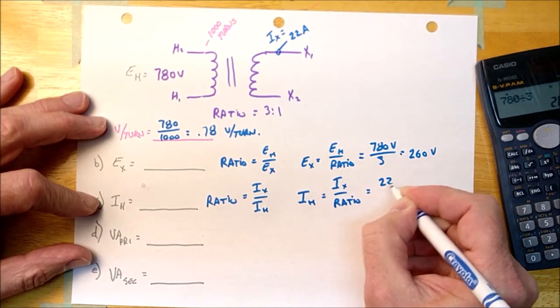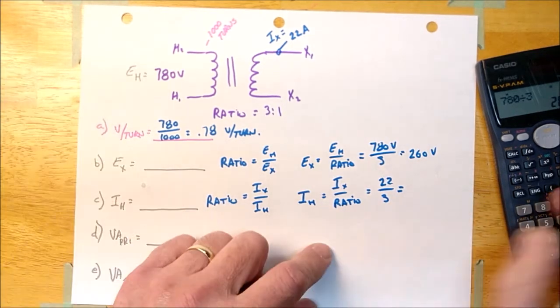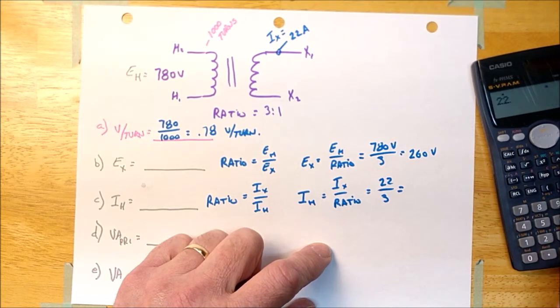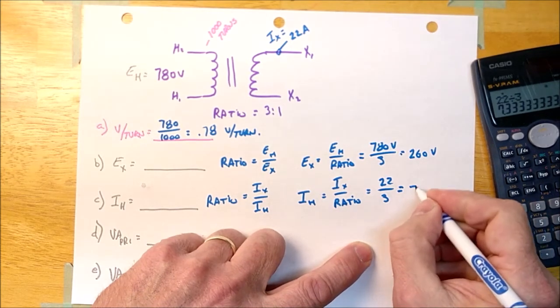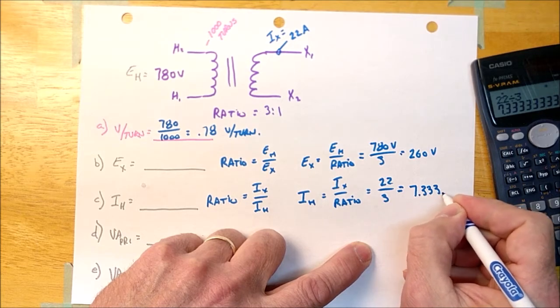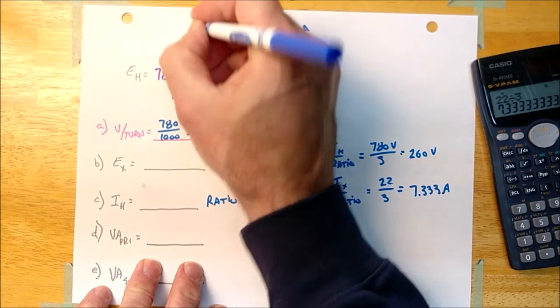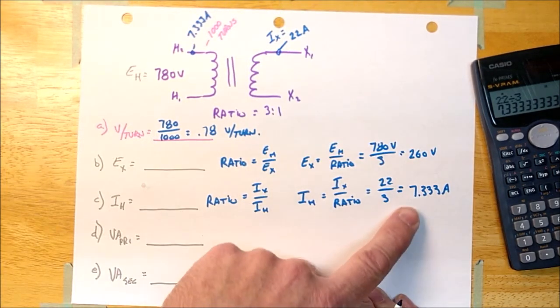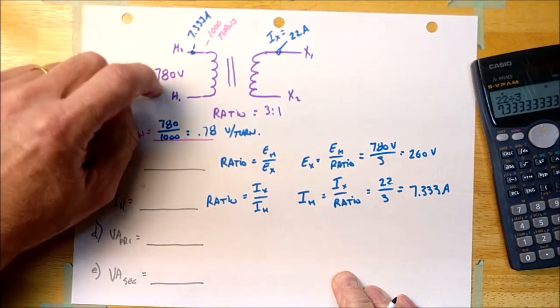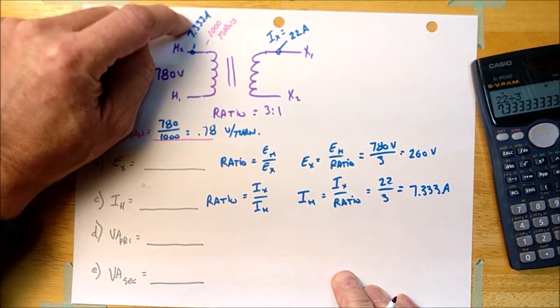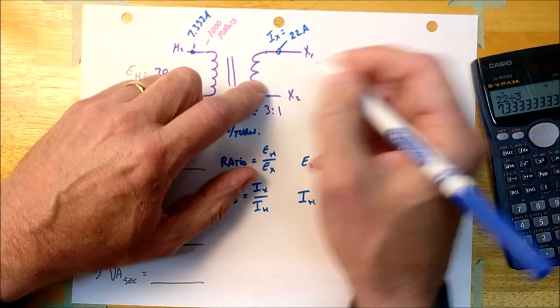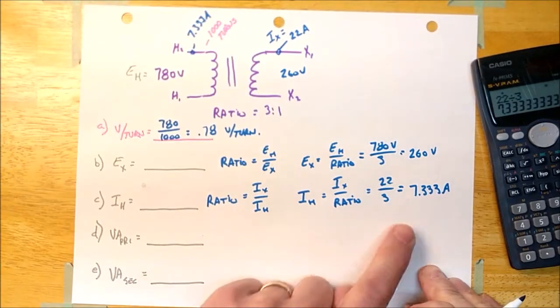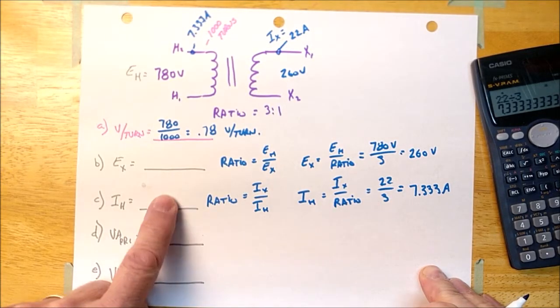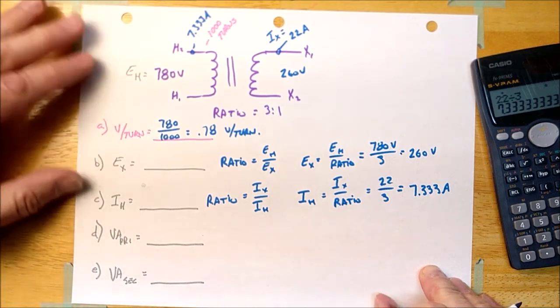IX is 22, ratio is 3, so let's calculate this. 22 divided by 3 looks like this says 7.333 amps, okay, and that would be present right here, 7.333 amps. And again, we're going to stop here and make sure this makes sense. The higher voltage has got to have the lower current. And the lower voltage, we just figured out, is 260 volts, it should have the higher current. So I'm pretty confident that this is okay so far, guys.